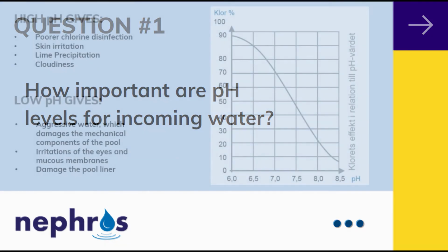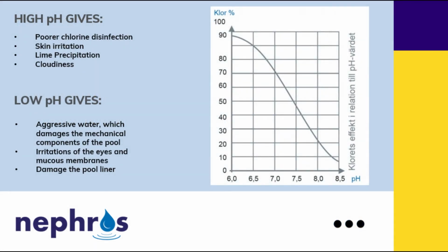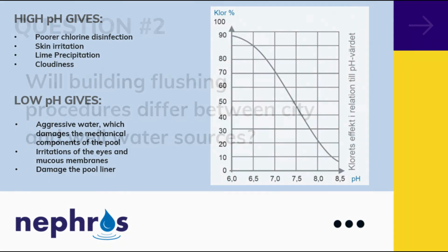So in the graphic, I have an example of that, and it really shows the effectiveness of free available chlorine. Now, we could show other charts, but really balancing the water chemical challenge is really important because in order for us to protect ourselves from piping, they add phosphate, which enhances biofilm formation. So it's really important to keep those chlorine levels up because, as you can see, as the pH goes up, the effectiveness of that chlorine product goes down. So it's important to control or to know what the pH is with respect to the disinfectant.